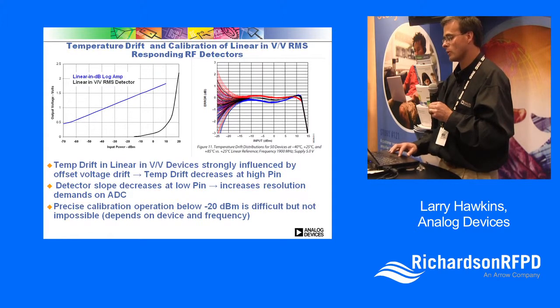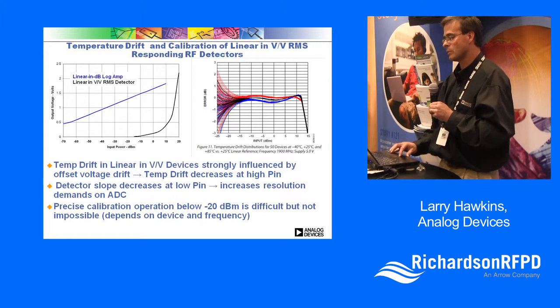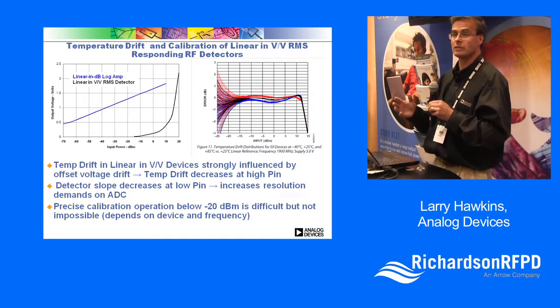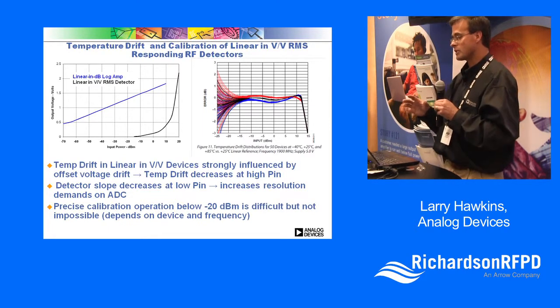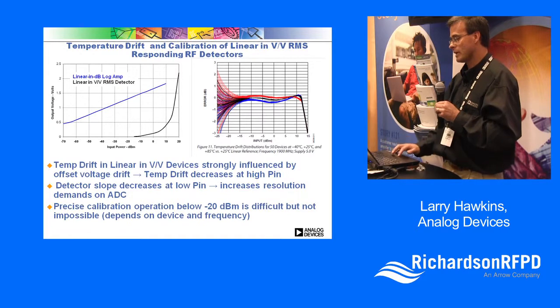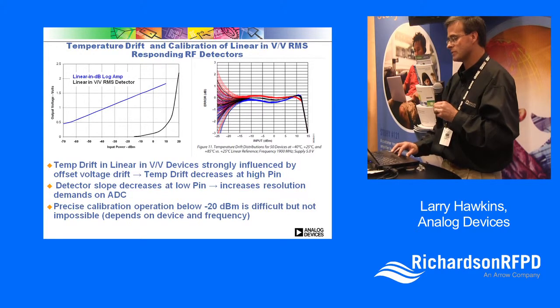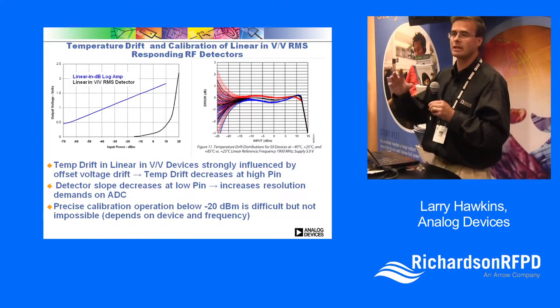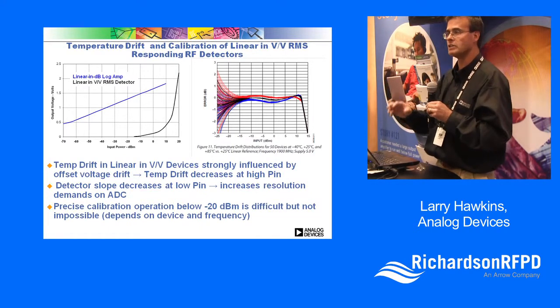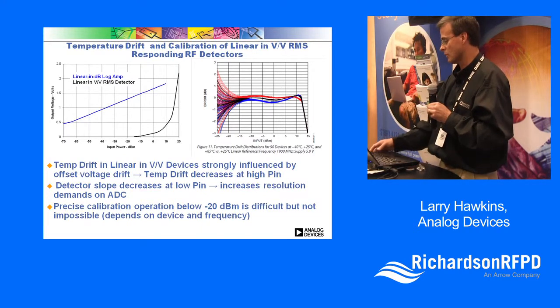As you go lower and lower in power level, you are further along the slope where the output isn't changing as much with power level. You also get more temperature variation at the lower power levels. You can calibrate a lot of this out — as shown by the black calibration line — but you won't eliminate all of the temperature variation at lower power levels.